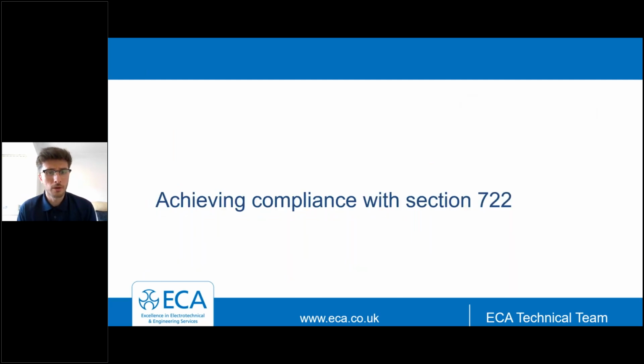So moving on to look at how to achieve compliance with section 722 of BS 7671. Of course, parts 1 to 6 are the general requirements for electrical installations. Then we have part 7, which looks at different special locations and special types of installations. These types of installations generally introduce additional hazards and additional requirements. So section 722 specifically looks at EV charging, and we're going to look at some of the key bits within here today.